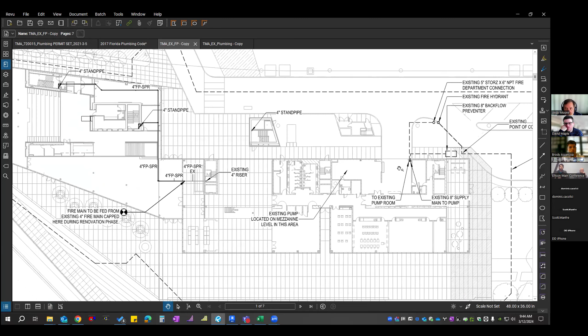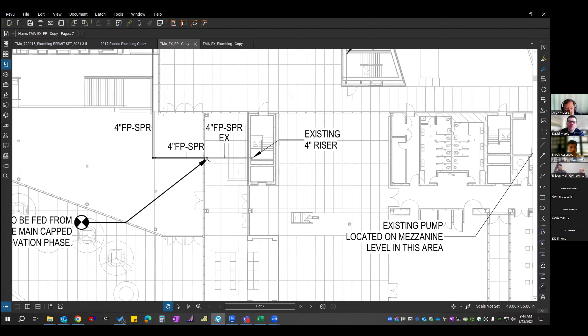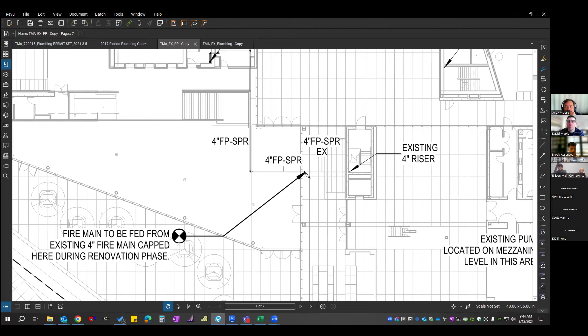The fire protection is fed from the existing building. So here's the existing building. Similar to the mechanical, the fire pump is located on the first floor mezzanine in the existing building. This doesn't show all the internal routing of the existing building, but we provided a main that goes down here, and a provision in the renovation for the new system to be extended from the existing. That fire pump has enough capacity to feed this new expansion. It's pretty simple - a 4-inch main, with risers in each stairwell that feed the sprinkler systems on the floor above.